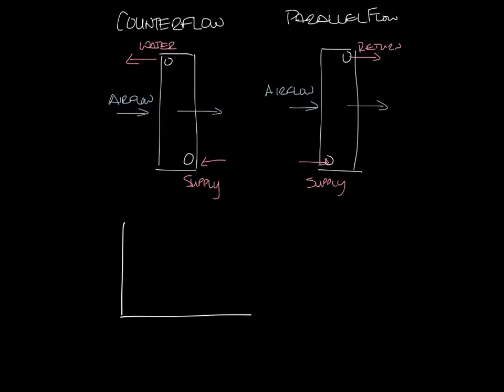The temperature profile of a counterflow water coil looks something like this. So the supply air is moving in this direction, and the temperature is increasing as it goes across the coil. The water flow is moving the opposite direction, so it starts warm, and the temperature drops as the heat is transferred to the airflow. The temperature differential between air and water are fairly uniform. This reduces the stress on the material in the coil, plus the discharge temperature of the air can be close to the inlet temperature of the water.